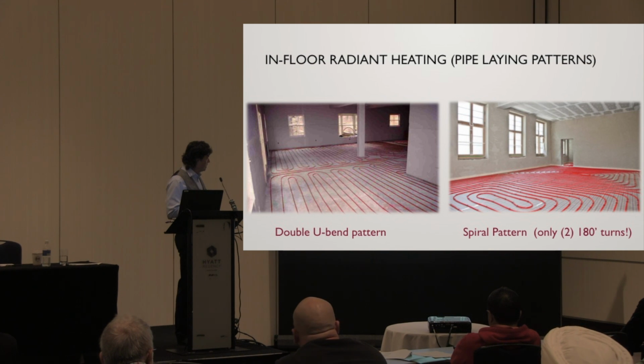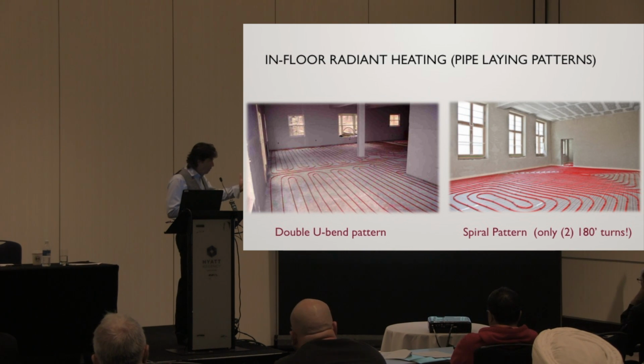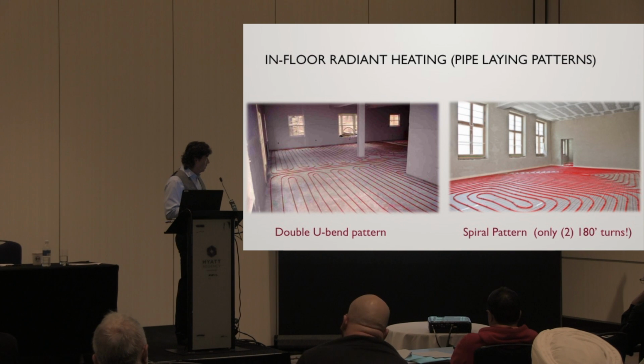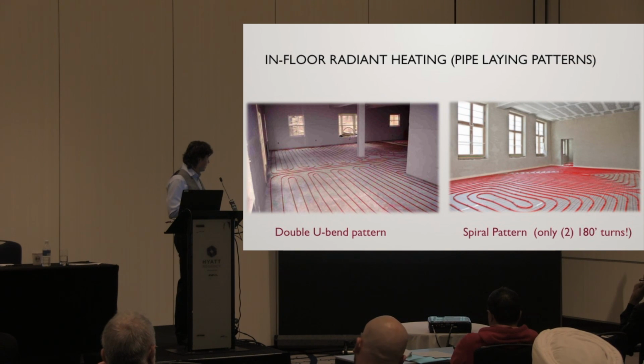Because what's going to happen is it's going to be the hottest there and it's going to fade. You'll see the return water temperature fade and fade and fade towards the middle of the room where you don't really need it. So in some applications, you can utilize the serpentine pattern if you really need to focus the heat there and you know you're going to have a gradient of return water temperature. So it's going to be quite a bit hotter over here, isn't it? Way more heat than there's going to be in the middle of the room. We'll talk about that in a minute too, actually.